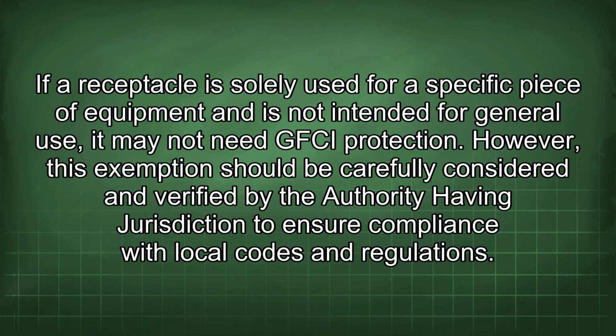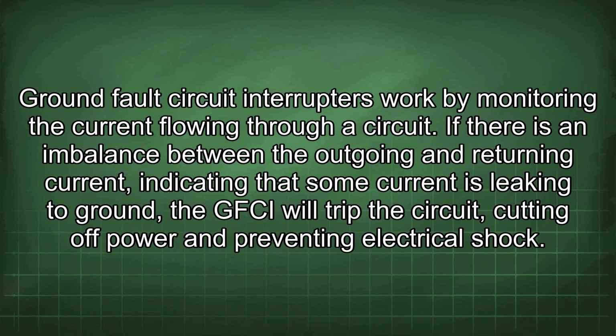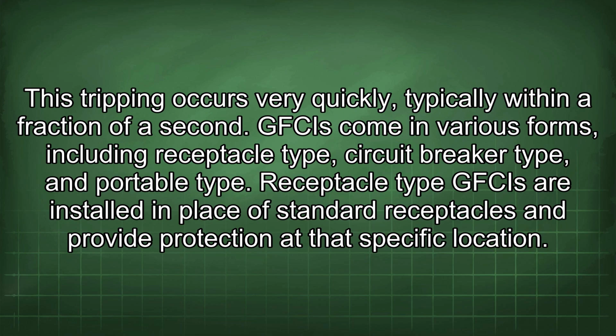Ground fault circuit interrupters work by monitoring the current flowing through a circuit. If there is an imbalance between the outgoing and returning current, indicating that some current is leaking to ground, the GFCI will trip the circuit, cutting off power and preventing electrical shock. This tripping occurs very quickly, typically within a fraction of a second.